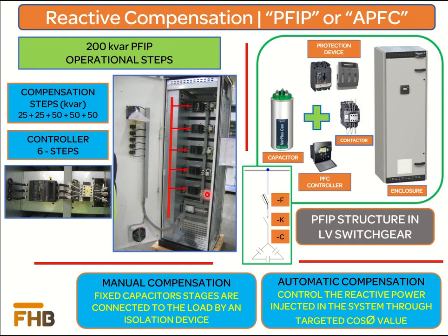For example, to make a 200 kVAr PFIP, we consider 5 stages — the first two stages of 25 kVAr and the next three stages of 50 kVAr. Each stage is connected to the load bus bar through cable connection. The power factor controller is installed at the door of the PFIP and is commonly available in 6-stage or 12-stage versions. Since our requirement is 5 stages, we use a 6-stage controller. Compensation can be done in manual mode, where the operator manually connects stages, or in automatic mode, where the controller monitors reactive power demand and connects stages by itself.